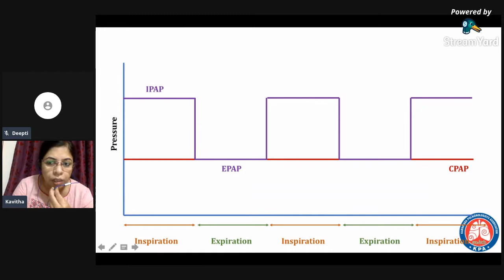What is C-flex? It is a modification of the CPAP device, where you can see here that throughout inspiration and expiration, the pressure has to be maintained in a normal CPAP. But in a C-flex, there is a modification where there is a small dip in pressure during expiration. So why is this required? If I am a patient who is getting a very high CPAP pressure, say I am getting 20 centimeters of CPAP, for me to breathe in, it is easier because it is helping me to breathe in with 20 centimeters of positive pressure. But at the same time, if I have to exhale against a pressure of 20 centimeters of water, it may be difficult for me to exhale against so much pressure.